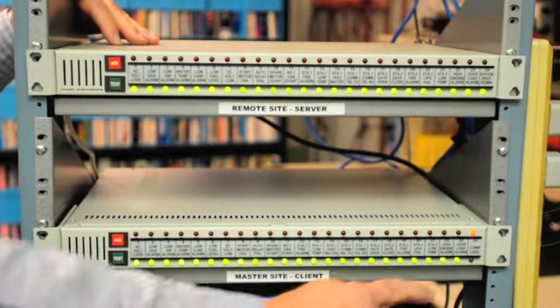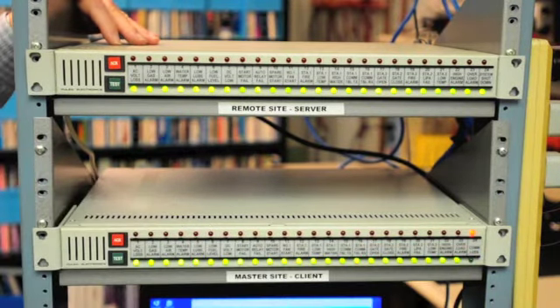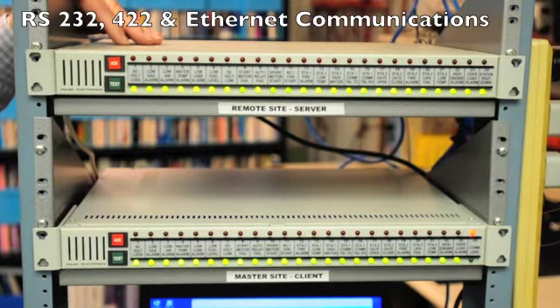It's the client. Right now, if you take a look at the unit, the last alarm point is lit over here. That's because, as a default, it shows loss of communications. Right now, I do not have the units communicating with each other. It has RS-232, 422, or Ethernet communications.